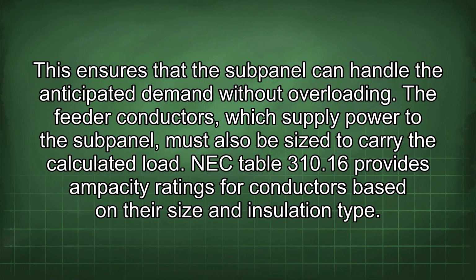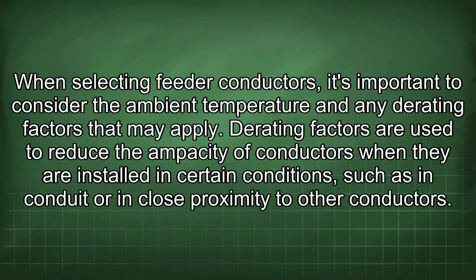NEC Table 310.16 provides ampacity ratings for conductors based on their size and insulation type. When selecting feeder conductors, it's important to consider the ambient temperature and any derating factors that may apply. Derating factors are used to reduce the ampacity of conductors when they are installed in certain conditions, such as in conduit or in close proximity to other conductors.